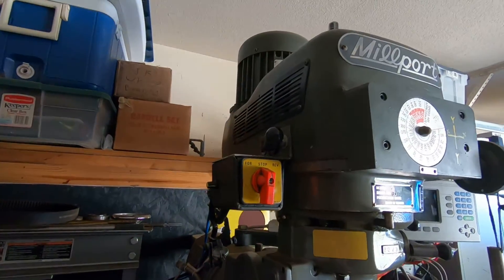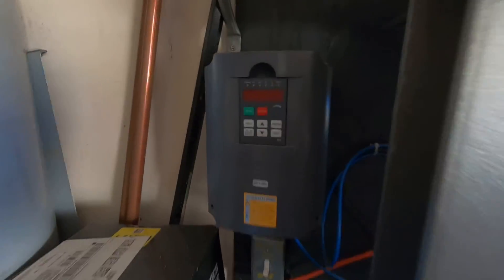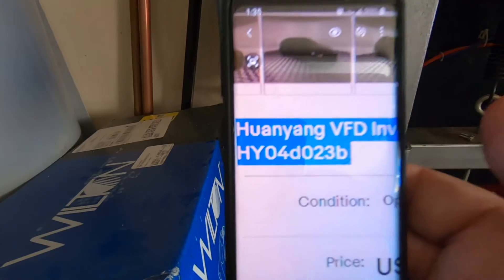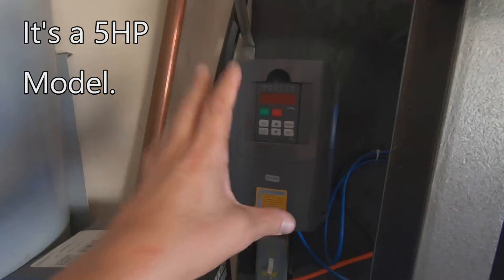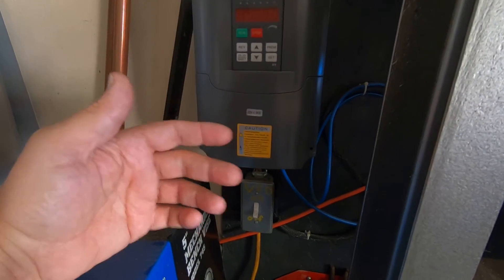What I ended up going with — for me it was a space-saving deal — was a VFD. Let me get the name of it because I honestly don't know how to pronounce it. This particular one is a five horsepower model. What it does is take 220 single phase and convert it to 220 three-phase, and it's very easy to wire up.